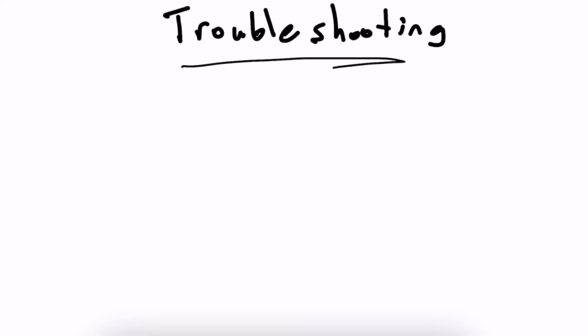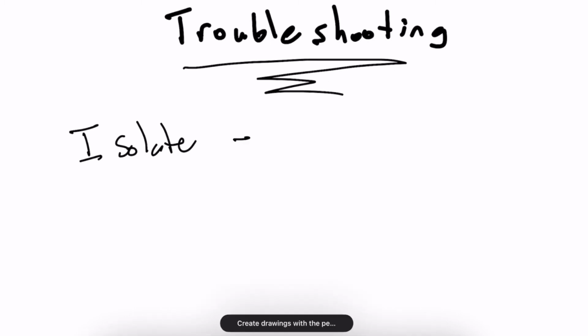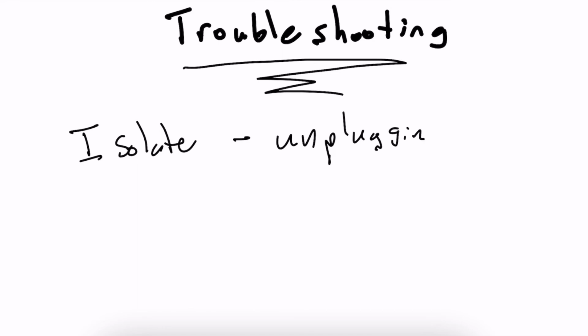Okay, so when you need to troubleshoot these systems, what do you do? Well, you need to be familiar with how they work. But typically, fundamentally, what you're trying to do is isolate the issue. What is the problem? Right? So figure out what piece of equipment or what groups of equipment are causing issues. So you can do this by unplugging devices, figuring out what device is causing the line isolation monitor to go off.